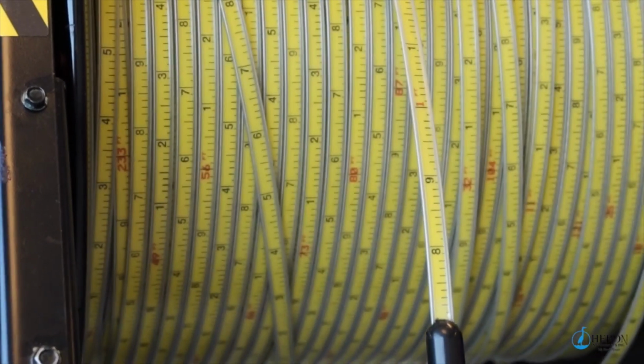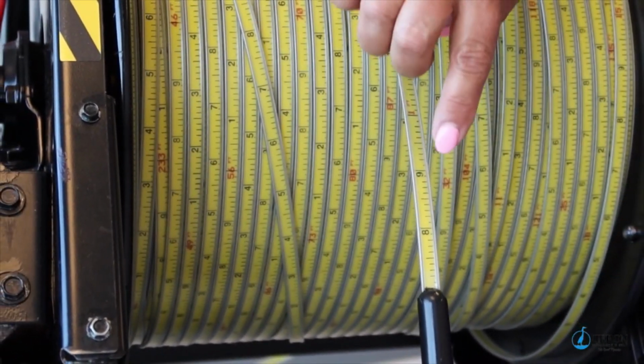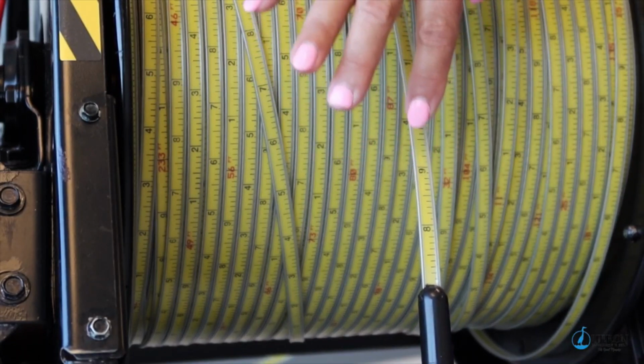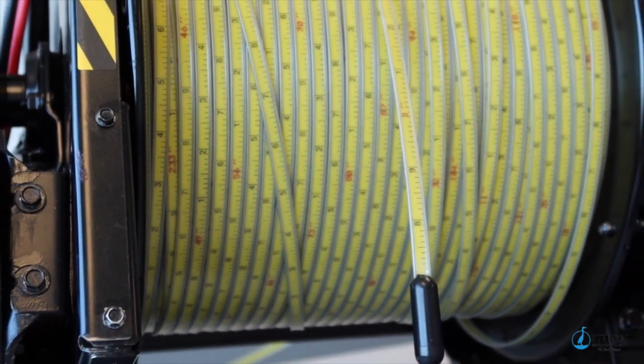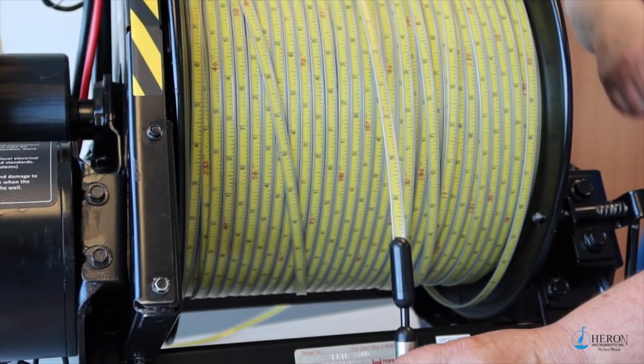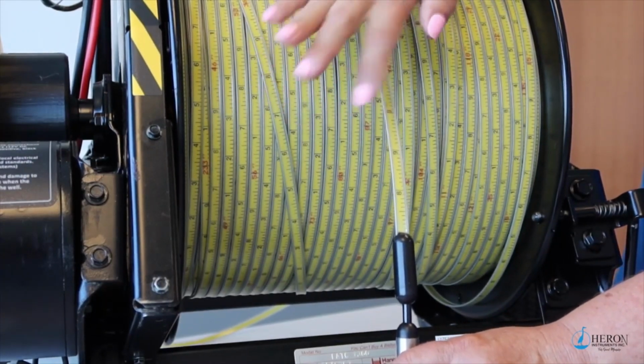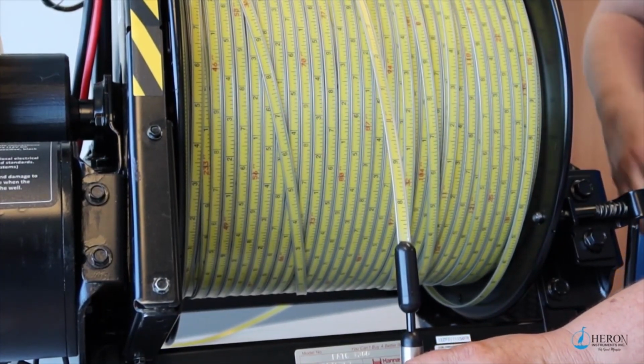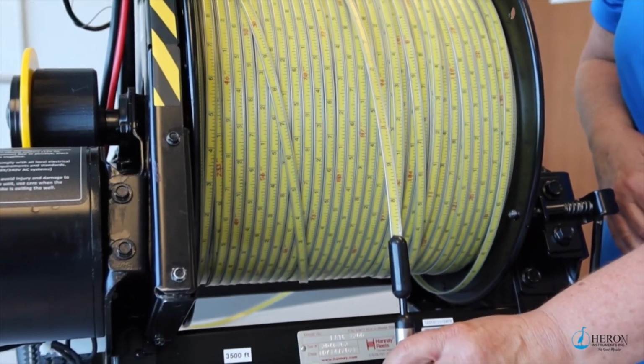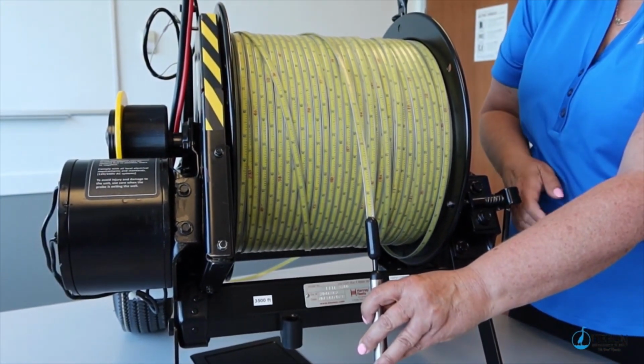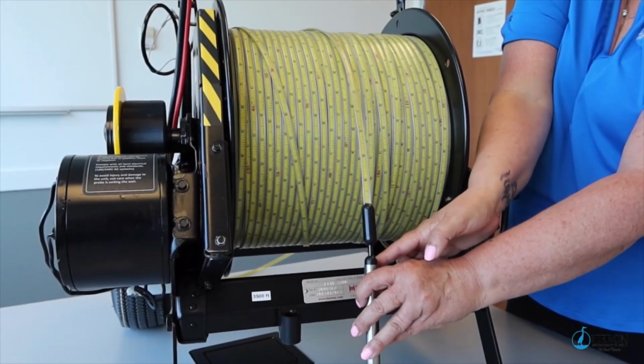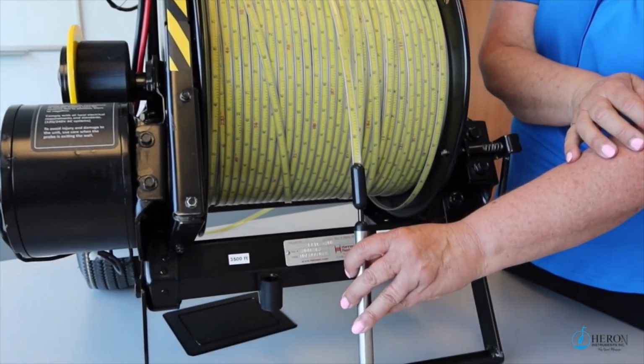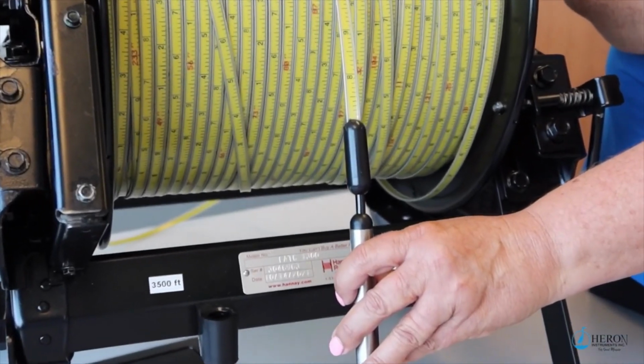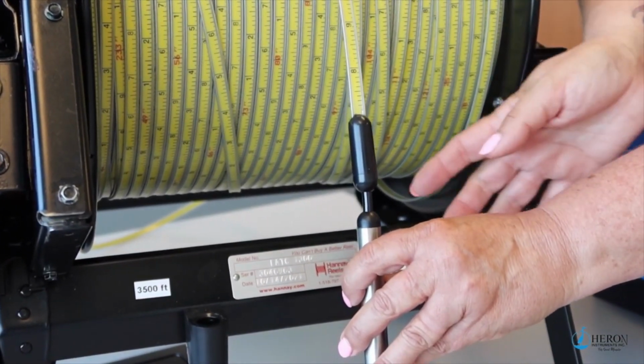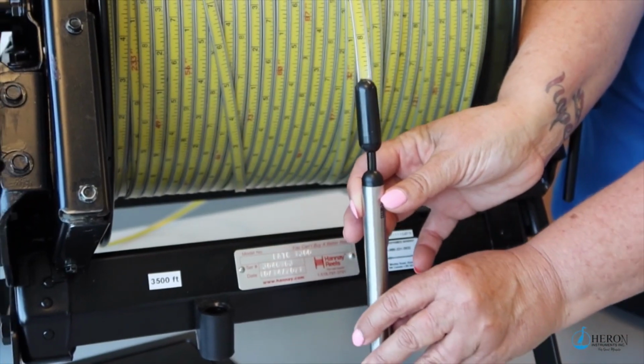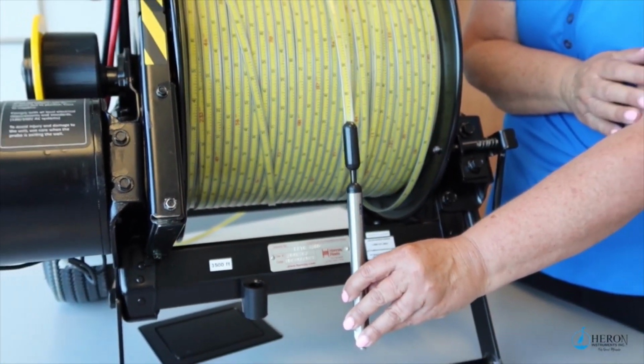The tape comes in either metric or imperial markings. The imperial markings are in engineering scale. The tape has a dog bone profile, meaning that it's rounded on either side and flat in the center, which helps eliminate sticking to the side of the casing. There is a shear pin style linkage above the probe, which will break away if your probe gets stuck in the well. Better to save your expensive long tape and lose an inexpensive probe, both of which are modular and replaceable as shown in our parts list.